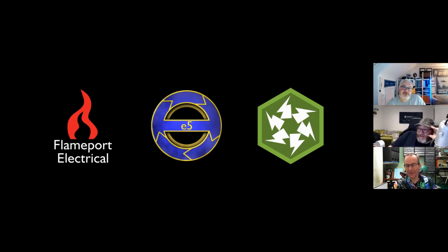In fairness, my words to the people at Schneider are, can you please tell me this in English? And if you tell me something, I'm going to ask you again, tell me in English, because we need to know. So, for instance, on my Isobar P here, if I highlight this, you'll see that there is a functional earth and neutral connection, which plugs into the busbar. So my question is, is there a link or a switch when it detects a rise in voltage on the neutral that links the neutral and earth? Now, we've just mentioned it in part 8 about linking the neutral and earth, but is it being done in the boards and the protective devices? These are questions we don't know, and their instructions don't tell us.